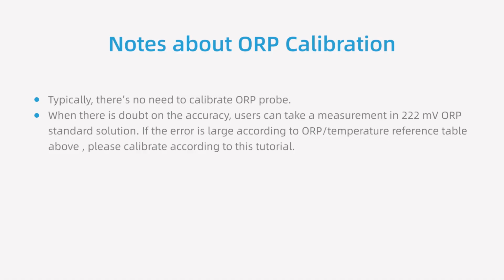Notes about ORP calibration. Typically, there's no need to calibrate ORP probe. When there is doubt on the accuracy, users can take a measurement in 222 mV ORP standard solution. If the error is large according to ORP, temperature reference table above, please calibrate according to this tutorial.